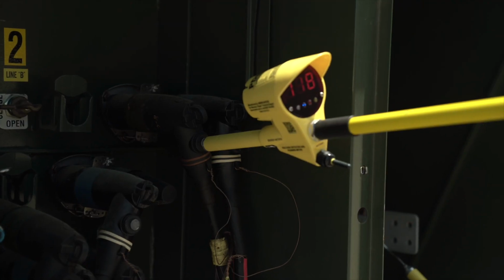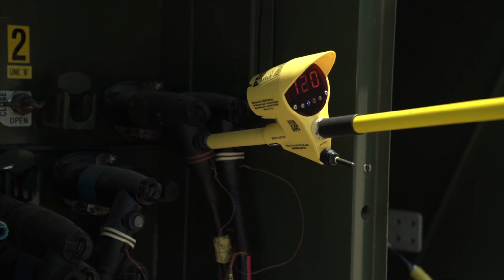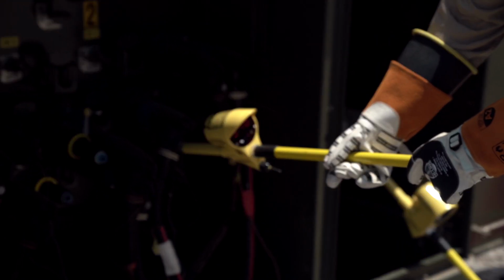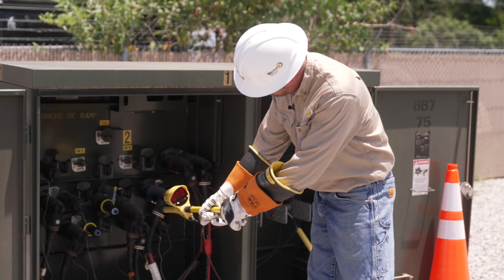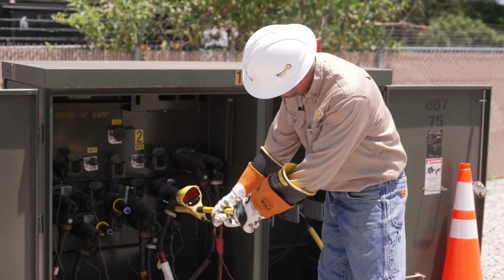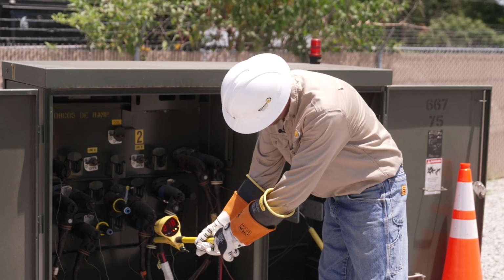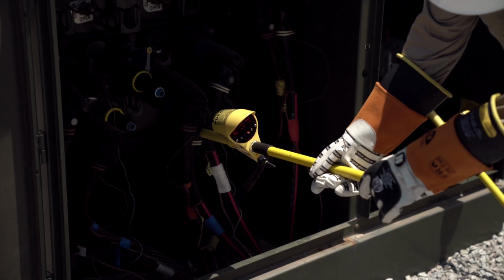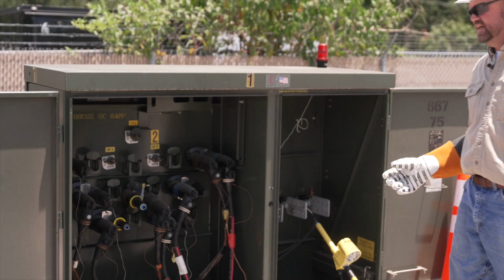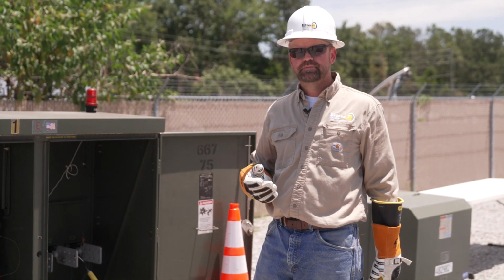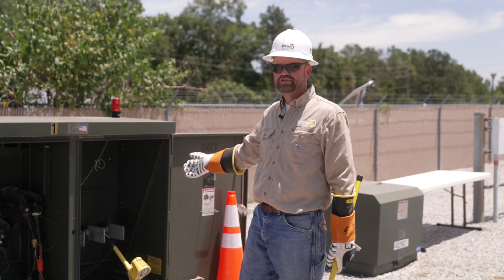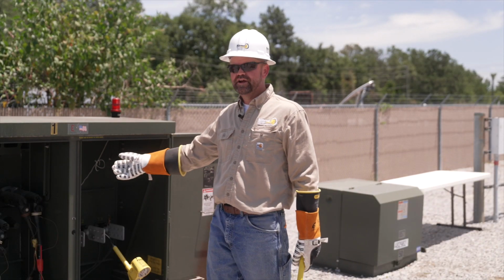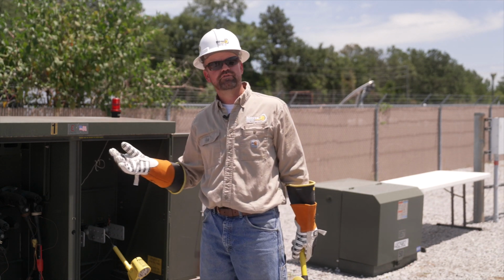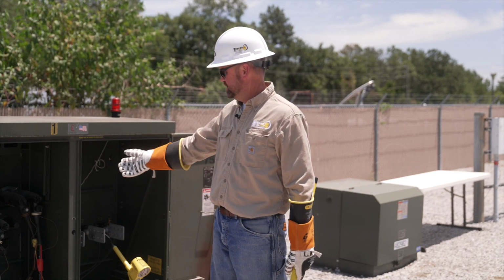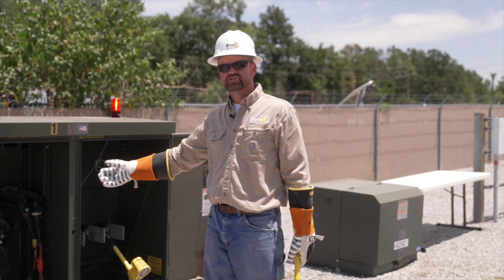So the H1B bushing, I have my blue light be near 120 degrees. My H2 bushing, I have my white light, my 0 degrees. And my X3B bushing, I have my red light coming up near 240 degrees. Again, I'm demonstrating phasing different potentials. I have 120, 208 on my secondaries. On my primary, capacitive test points can range anywhere from 2 to over 300 volts. So I determined my H2 bushing is in fact the source of my X3 secondary bushing.